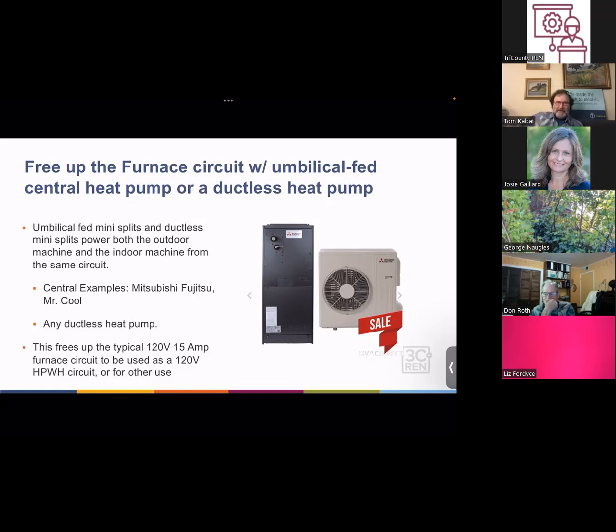Okay, and then this slide's covering that idea of an umbilical fed central heat pump. What you see on the right side of the picture is the outdoor unit of a heat pump. It gets power to a circuit out there, and then there's a line set of refrigerant and the electrical signal and power coming over from the outdoor unit to the gray box there, which would replace the furnace. That's the indoor unit, and the indoor unit gets its power from the outdoor unit. So together they're just on one circuit, and that freed up the furnace circuit. Also, any ductless heat pumps are powered the same way from the outdoor unit. And so that frees up the furnace circuit. Next.